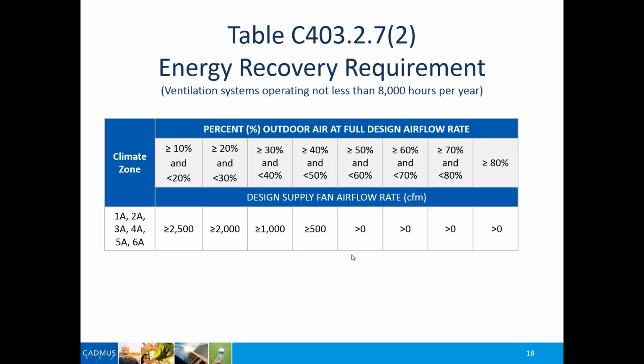And obviously, the higher your outside air, for buildings that operate pretty much year round, you will always have to have energy recovery ventilation. So when you start looking at 50% to 60% outside air, that greater than 0 means that any supply air fan system you put on there will actually have to have energy recovery ventilation. So we're starting to bring in high amounts of ventilation air into the particular building.